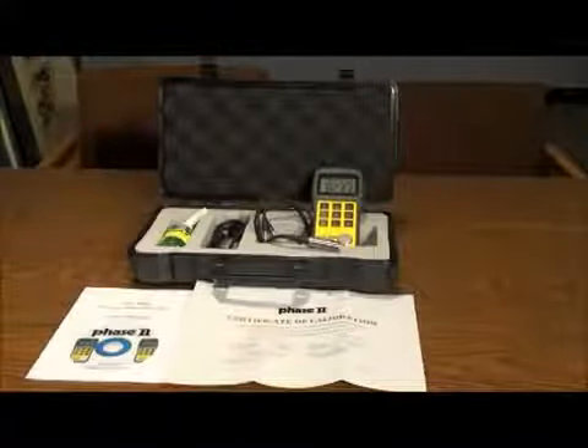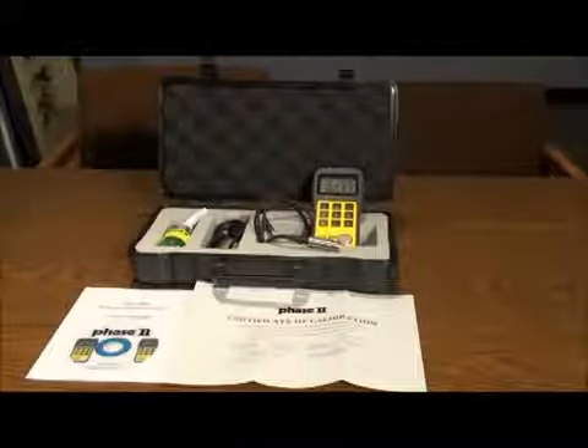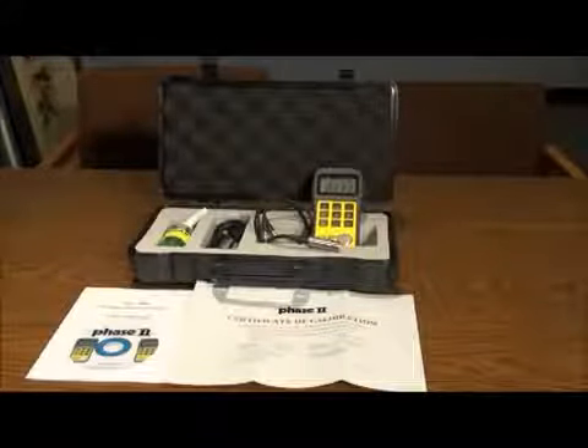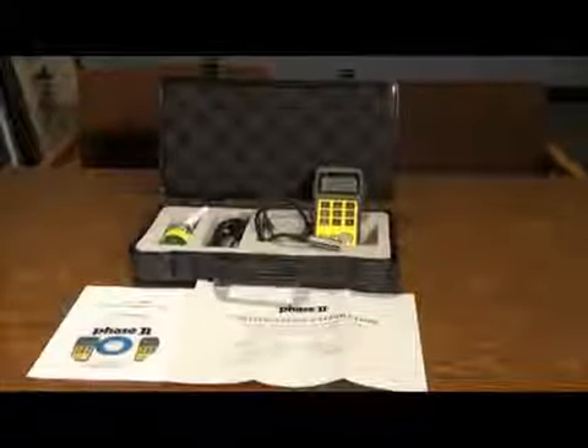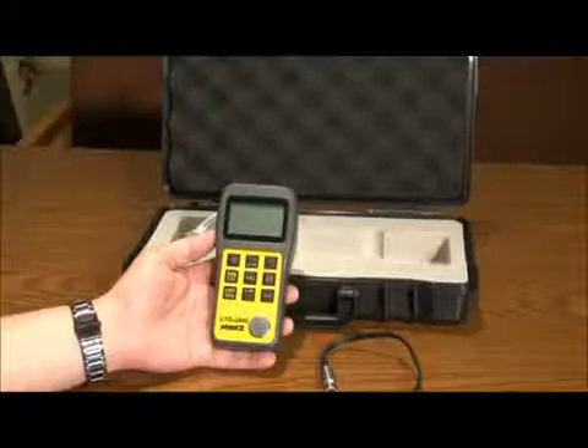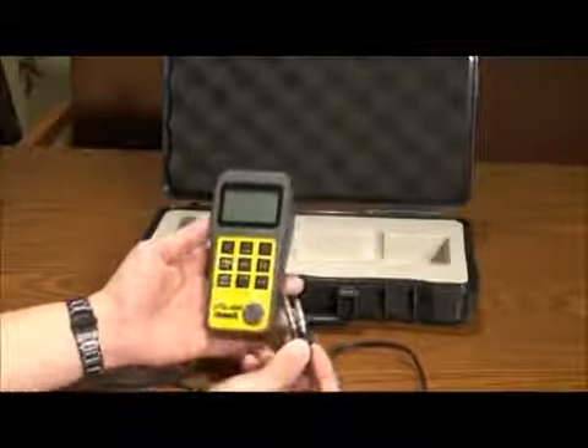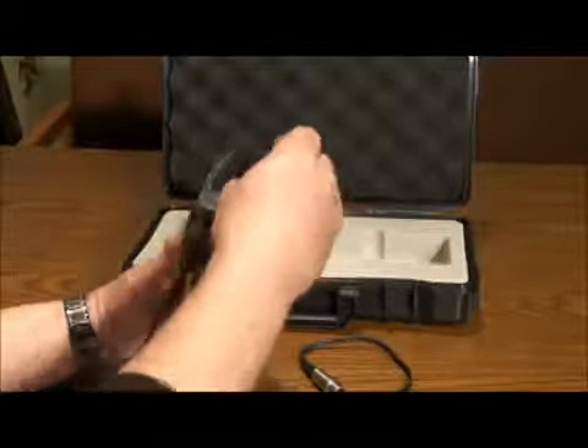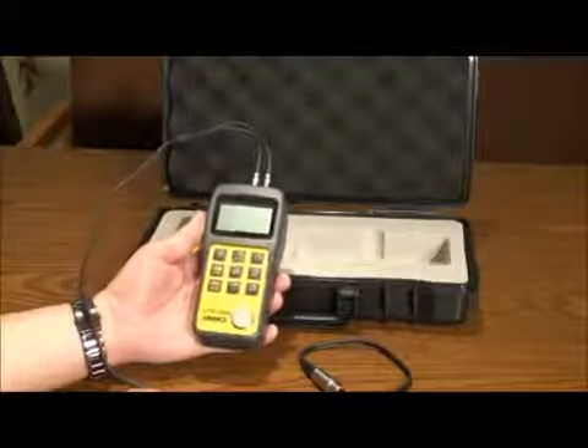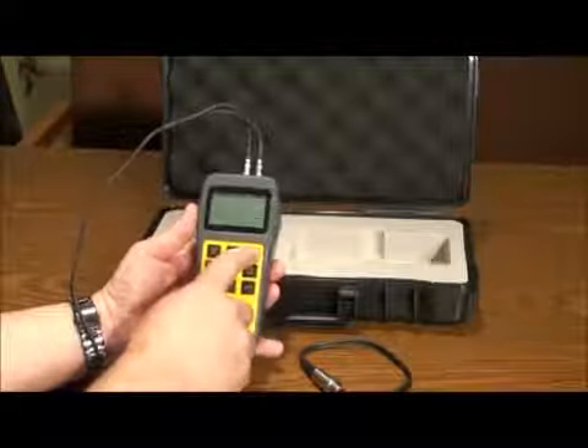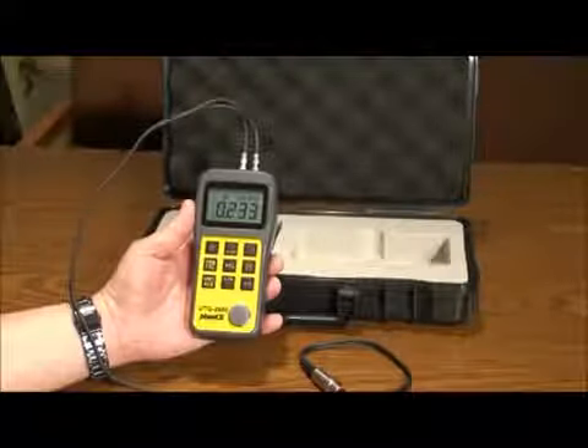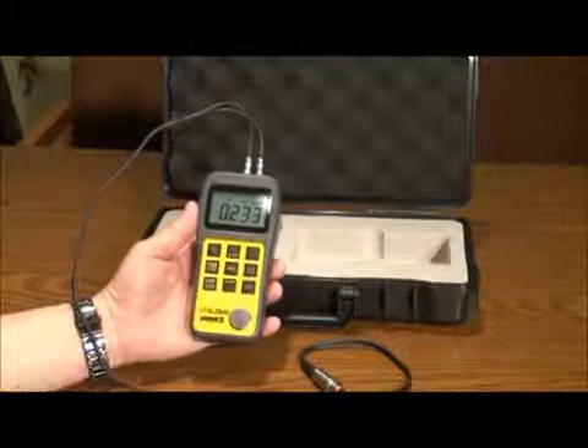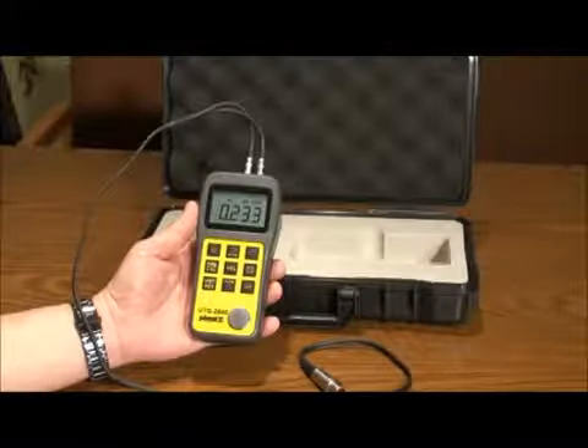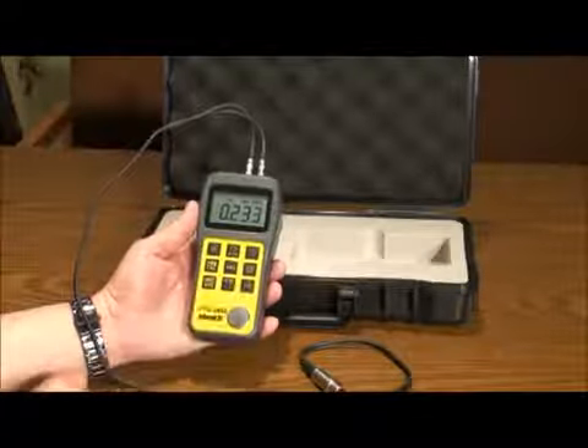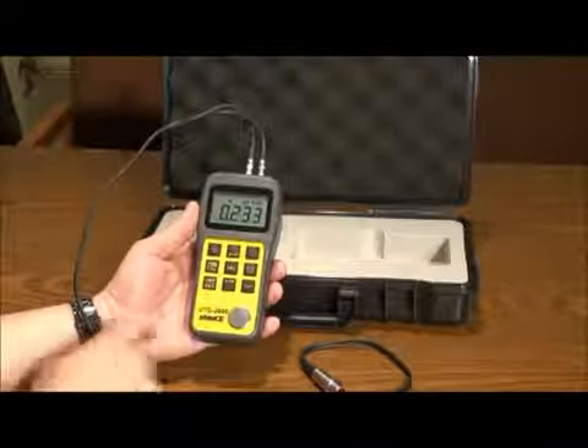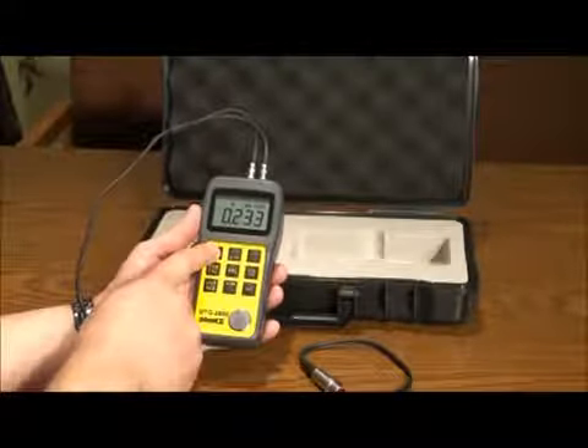Now let's move over to the operation of the UTG 2800 and see how easy it is to utilize the different functions, taking tests, and obtaining results. To begin, insert the plugs of the transducer into either of the plugs in the gauge. Press the power button top right to bring up the interface. You can power down the unit by pressing the same button. The button on bottom right is the enter key. To turn on the backlight, press the button on the top left and press again to turn off.